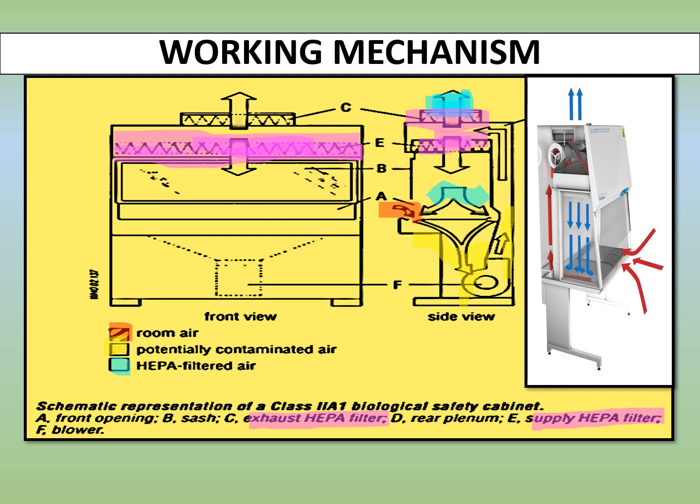In the inward flow system, there is a blower that pushes the air upward, where it moves out of the system through HEPA filters. Hence, it protects the environment. An important point to consider is that not all of the air is filtered out. Some portion of air is recirculated after going through a HEPA filter.